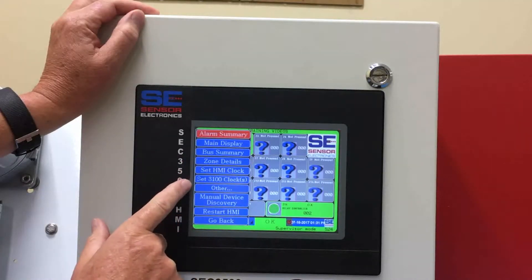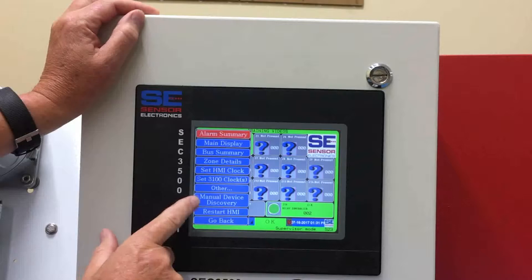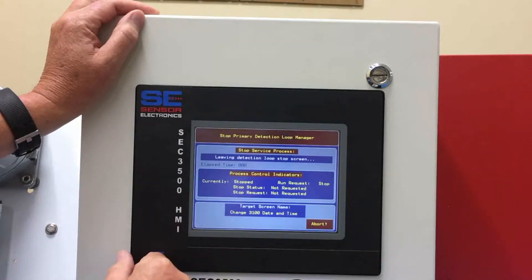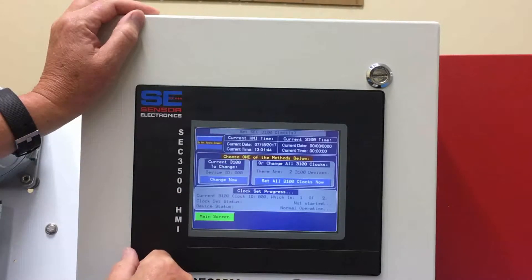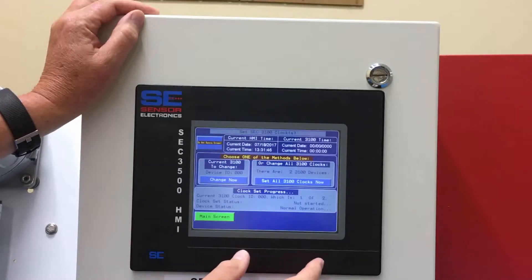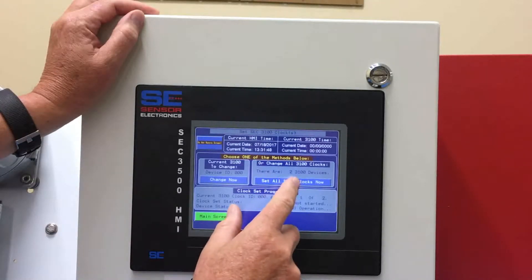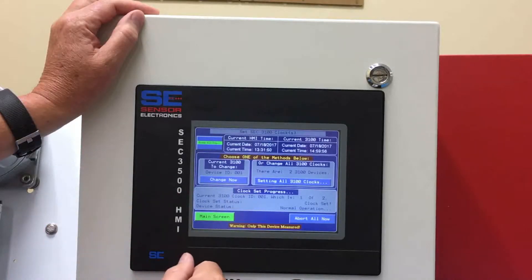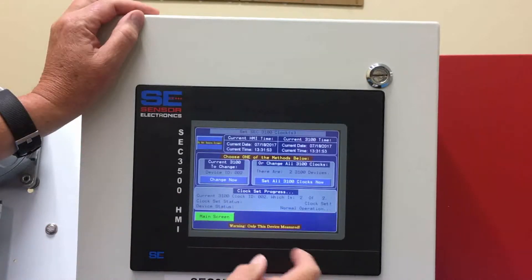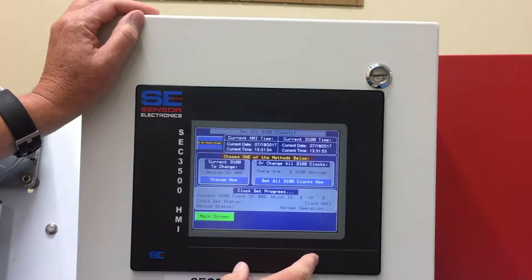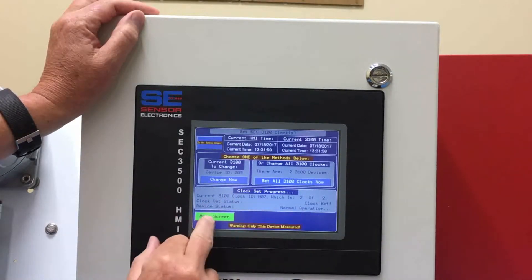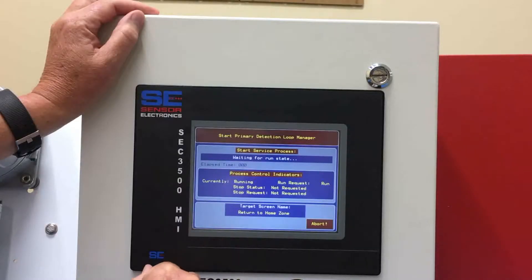It also provides you the option to set all the clocks inside of the detectors. What this does is set all the clocks — because we have real time clocks in all the gas detectors — to the same clock time and date of the HMI controller. It goes through and resets them all so that they will all match up.